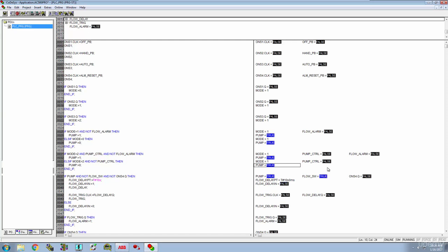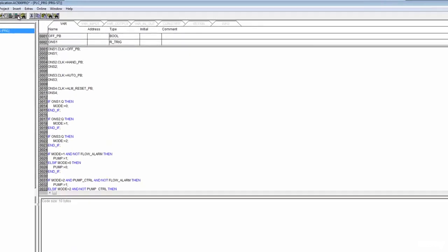So our flow switch is now closed, and we should not get another flow alarm at the end of 10 seconds. So we're waiting, we're watching, and no, I'm not seeing a flow alarm. Good. And then if I open this flow switch back up, there we go. We get a flow alarm, but we're getting that flow alarm a little too fast, which tells me that our timer's count is not being reset. We want to give it a fresh 10 seconds every time.